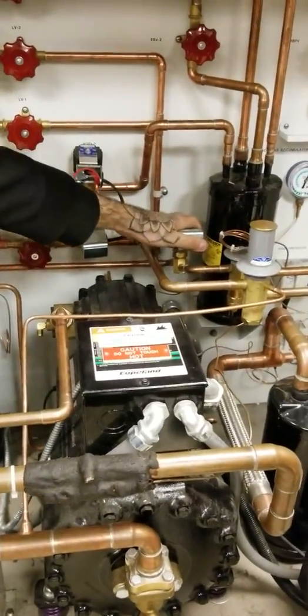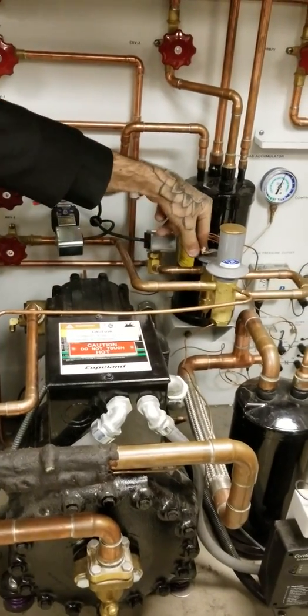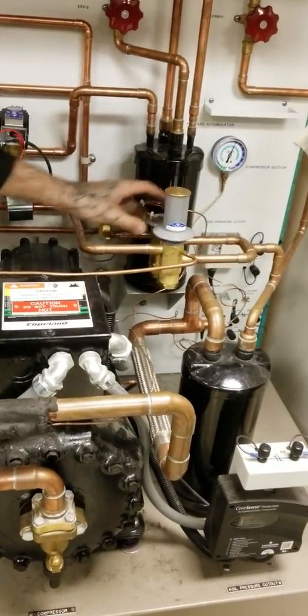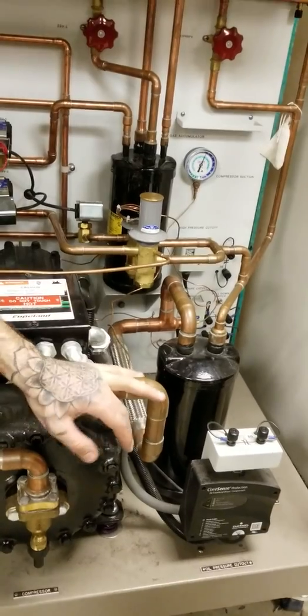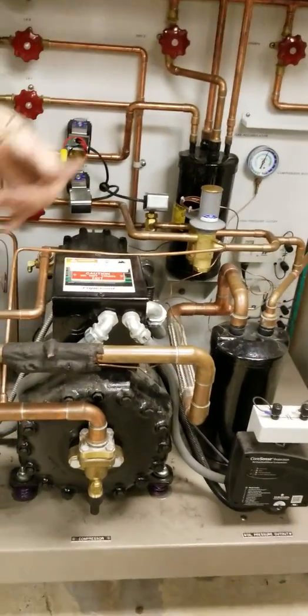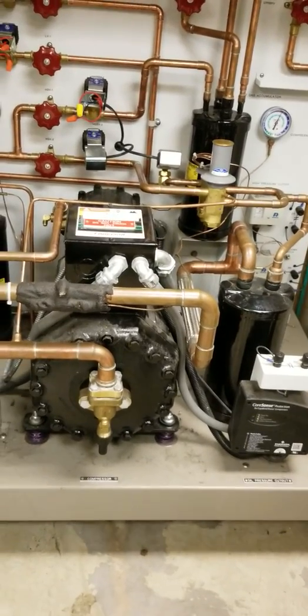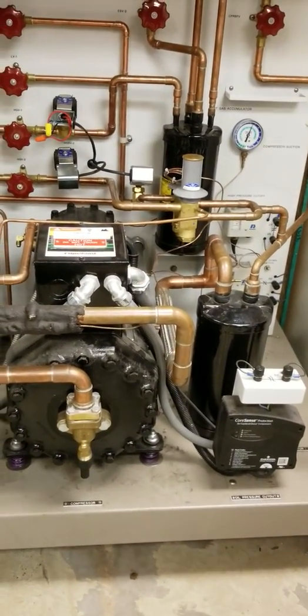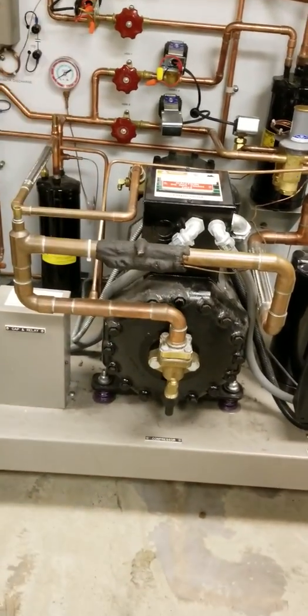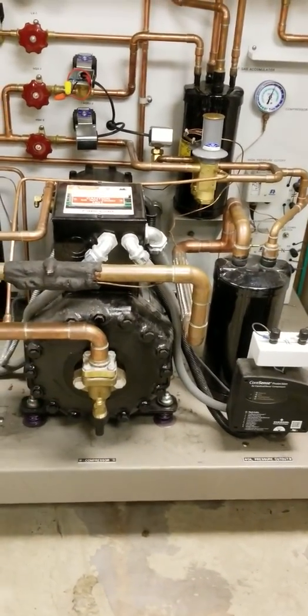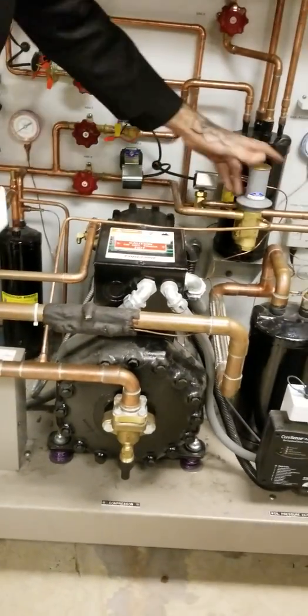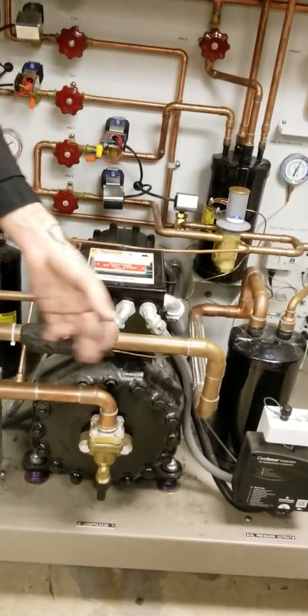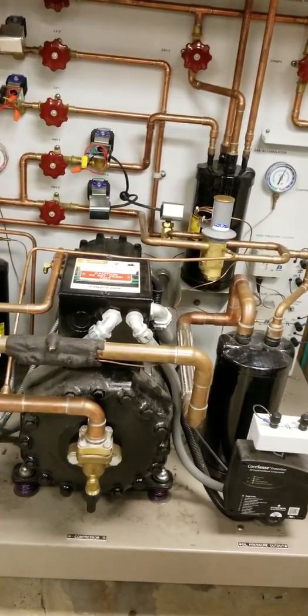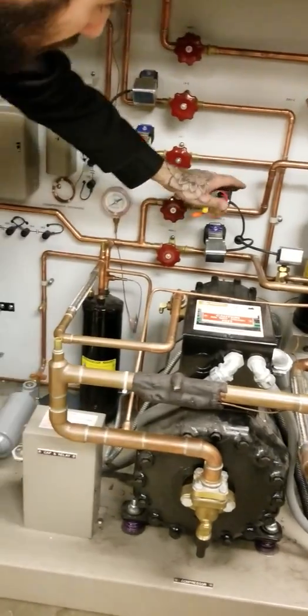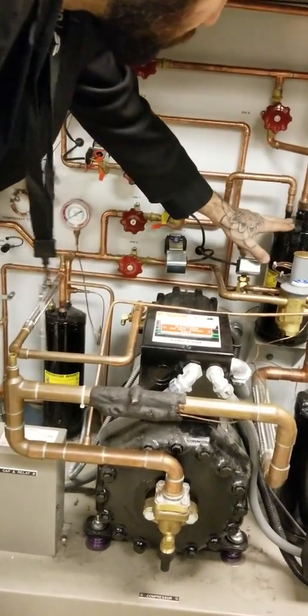another solenoid that's going to control when we send refrigerant to our defrost valve, which is just a TXV that's going to allow us to not have an excessive pressure drop. Because this thing's going to freeze. It might develop ice. We're going to get into cold temperatures, low pressures. And so if we run this thing dry on refrigerant and we're starving it, and there's not enough refrigerant making it back because it's collecting the coldest in, you're going to have a compressor working hard, getting really hot. So this valve will spill refrigerant into it to balance it out and keep that pressure stable before you have a large pressure drop. So your solenoid valves are then going to come through into your liquid receiver.